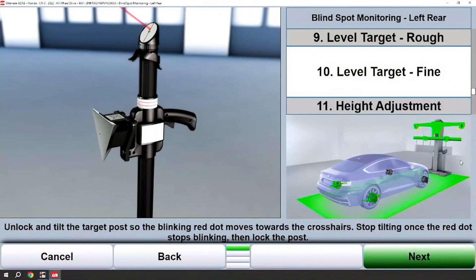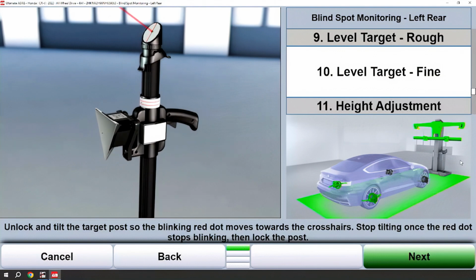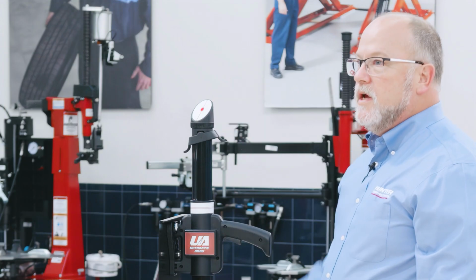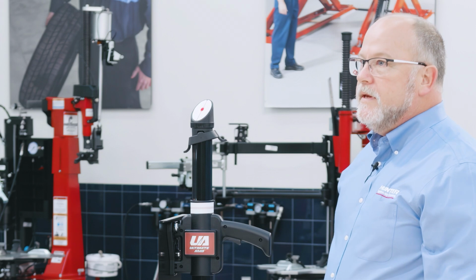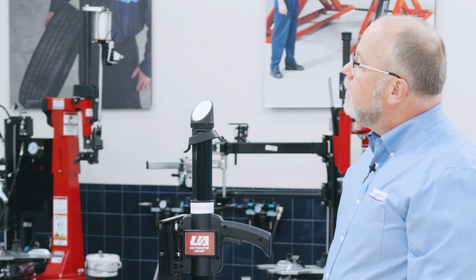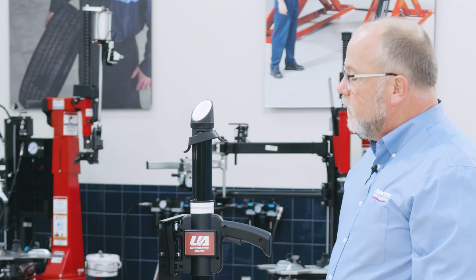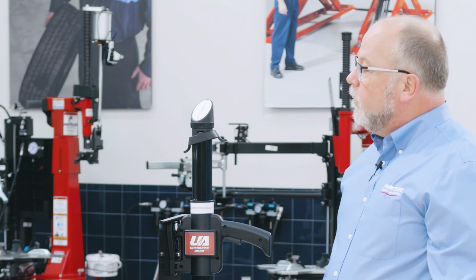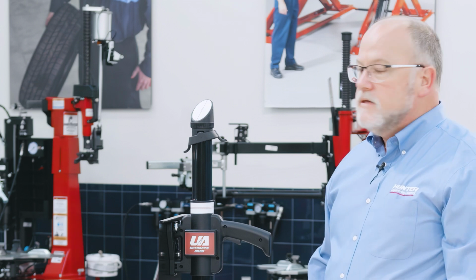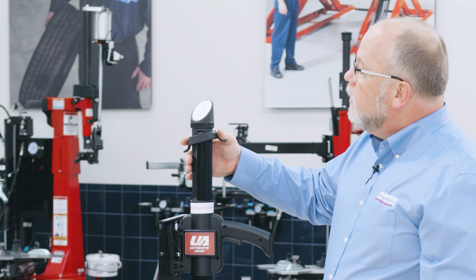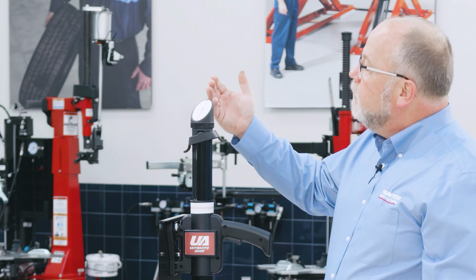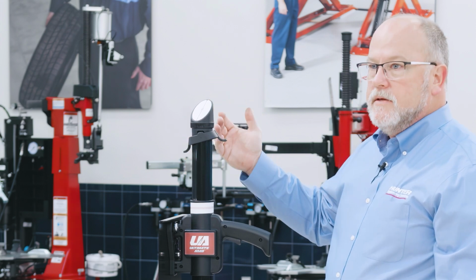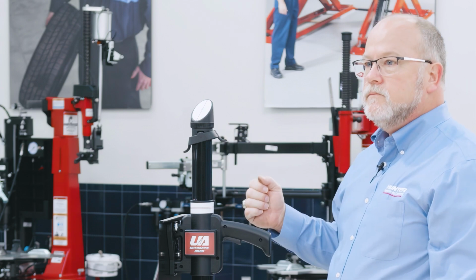Next, we need to make a fine adjustment on this stand. This is where that red dot will flash and a time of flight measurement will be taken. If it's perfect, it will go ahead and progress. If it were not perfect, you would need to unlock the stand and move up and down on the line until the dot stopped flashing.